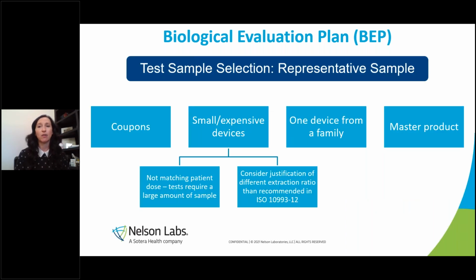So I just wanted to talk quickly about representative samples. You can use coupons, so something that represents your sample. If you have small or expensive devices, typically we don't want to include 1,000 devices in an extract if the patient's exposed to 2, right? So we want to think about patient exposure and consider justification of maybe a different extraction ratio. And with small, expensive devices, we'll also consider the use of coupons. If you have a product family, you could pick one product that represents all the materials and processing for your family, or you can make a master product. We also call it a Frankenstein, where you may put together a few different connectors or something to make your monster product that we would say represents your full device.